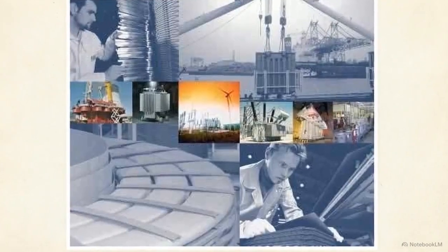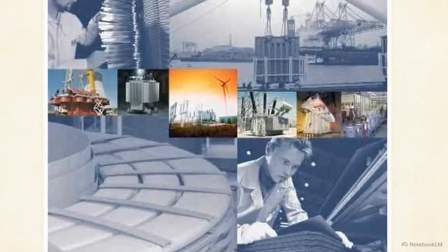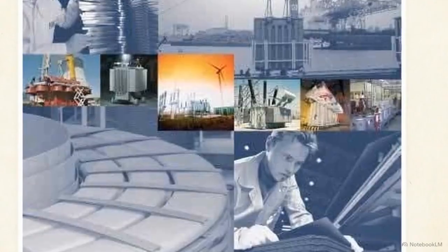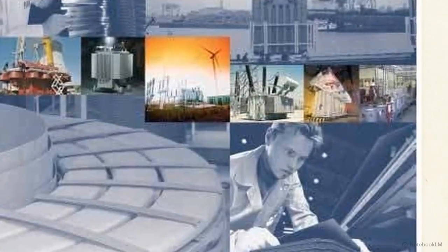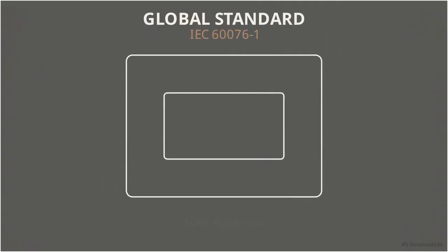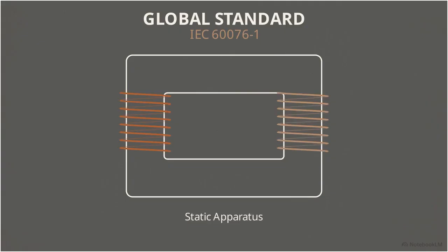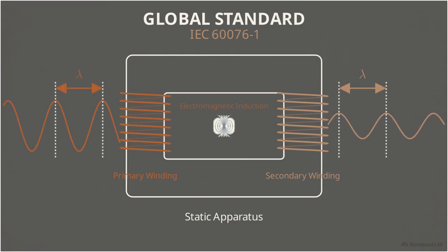To maintain this stability, the industry relies on strict, formalized engineering guidelines that govern the design and deployment of this technology across all sectors. The standard reference is IEC 60076-1. It dictates that a transformer is a static piece of apparatus with two or more windings, operating entirely through electromagnetic induction. Its specific mechanical purpose is transferring energy between systems. It takes a system of alternating voltage and current and translates it into another system with different values, while strictly maintaining the original input frequency.